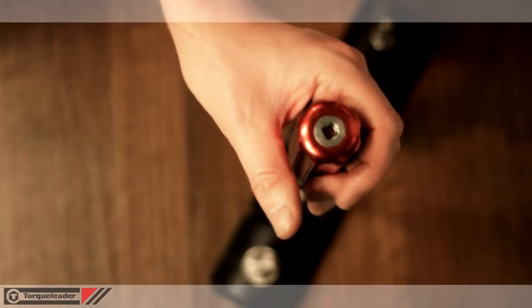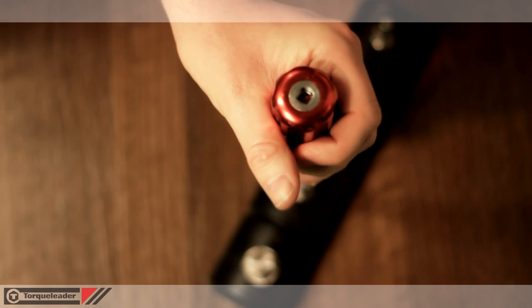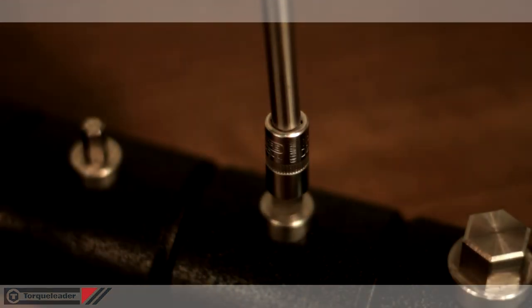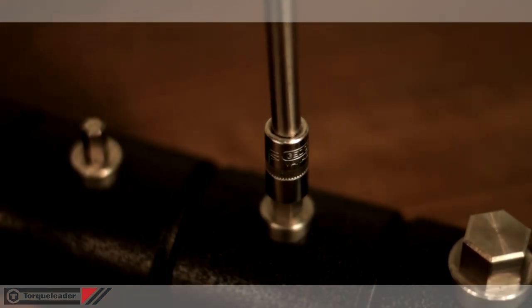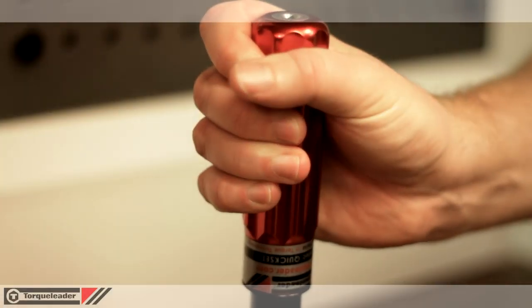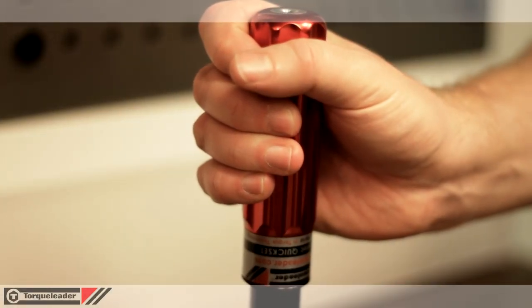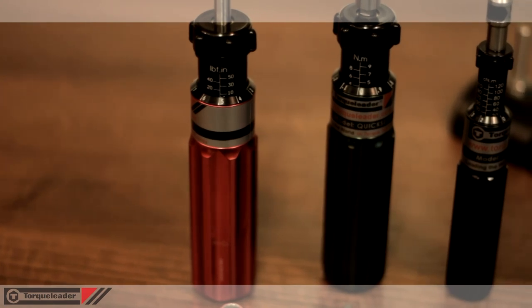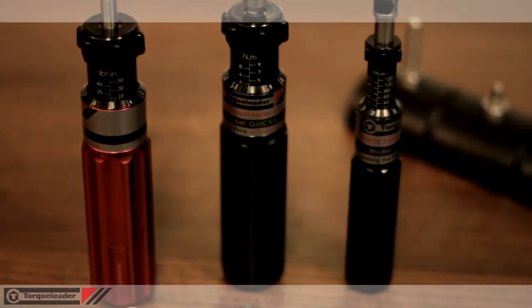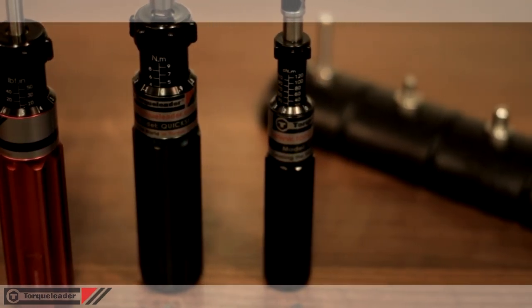At low torques, the risk of over-tightening the fastener is increased. The Quickset screwdriver eliminates this risk by slipping free at the set torque, making it impossible for the operator to apply more than the chosen value. There are 6 low shock resets per revolution, minimising operator fatigue.